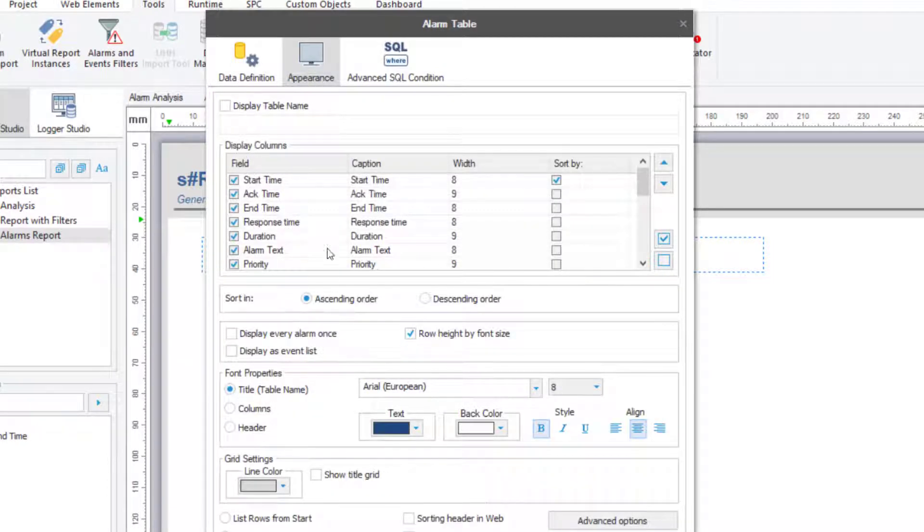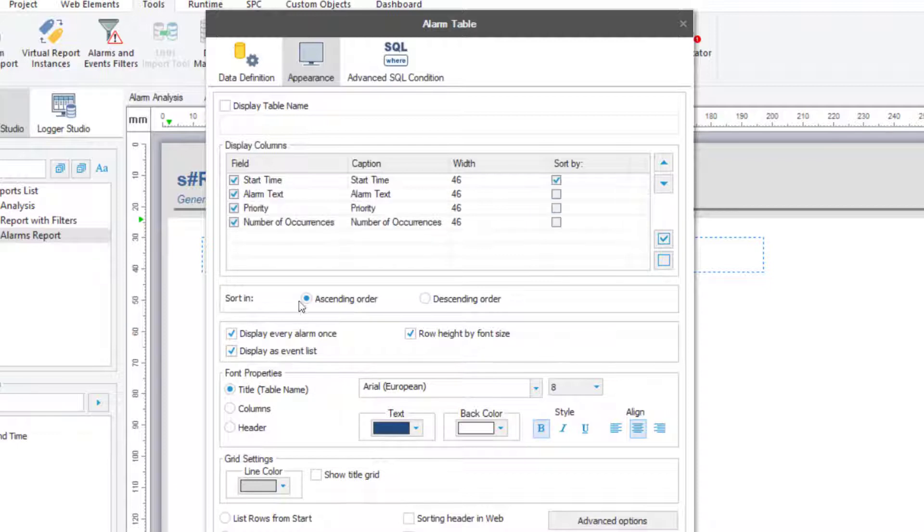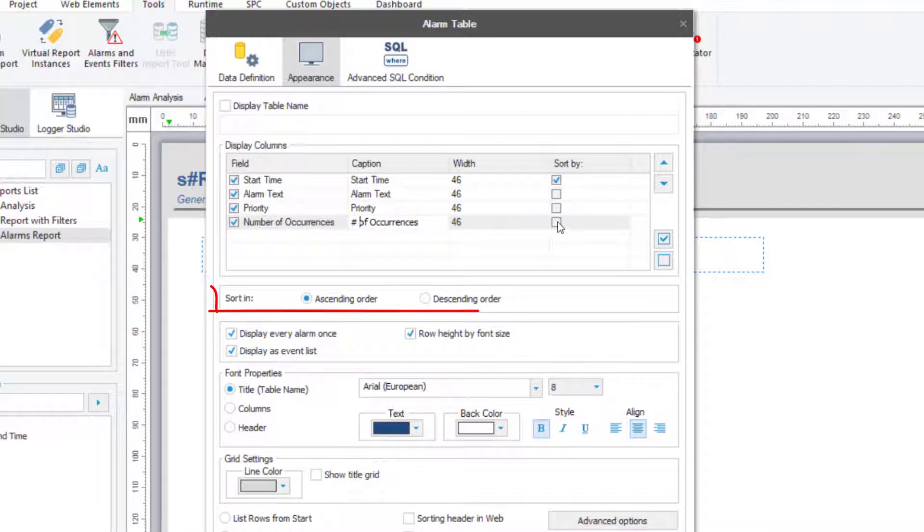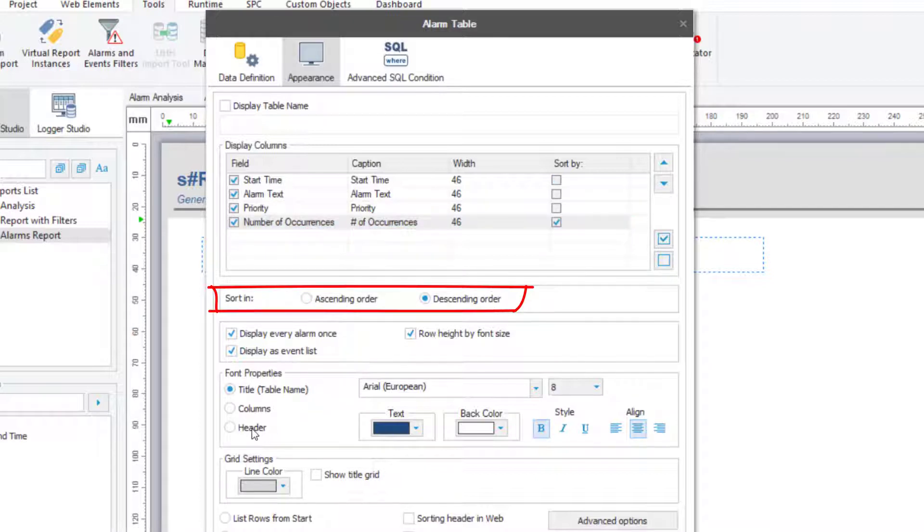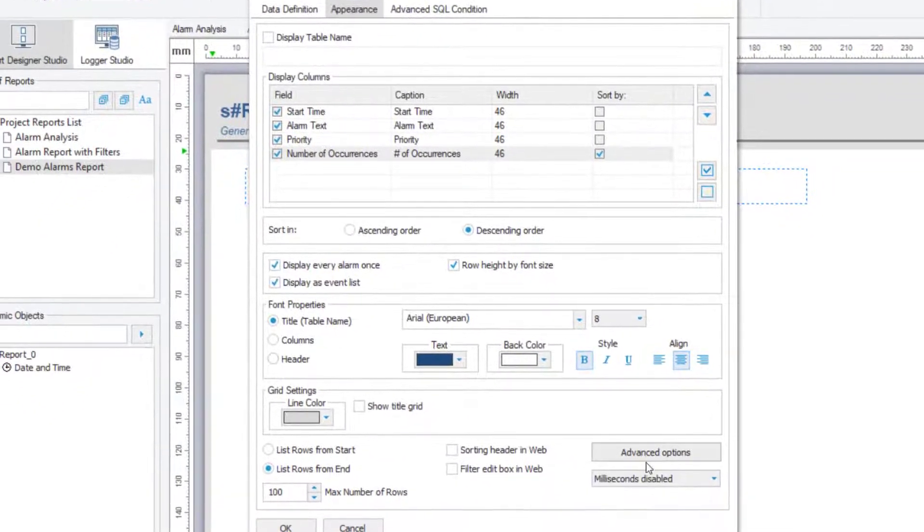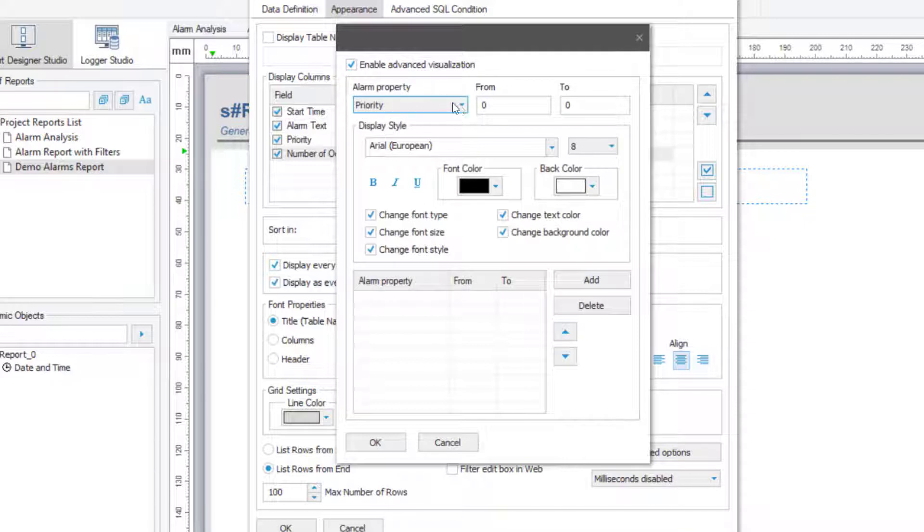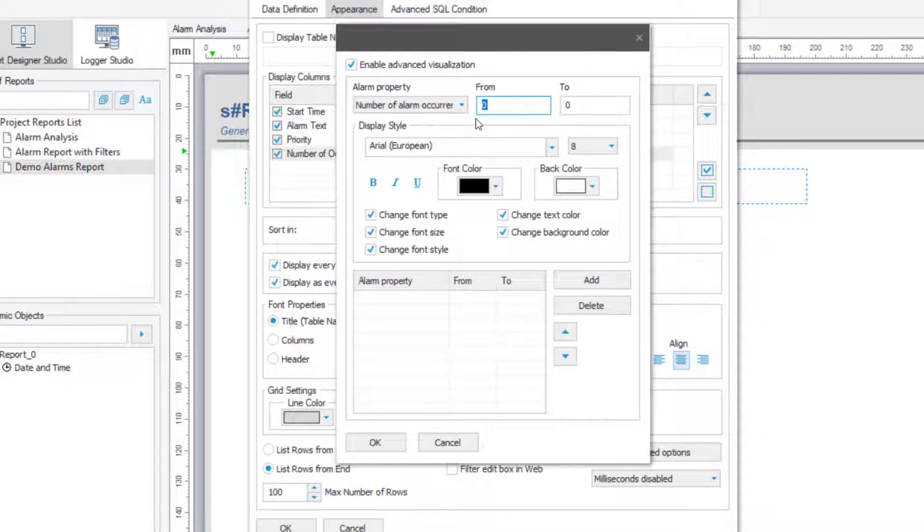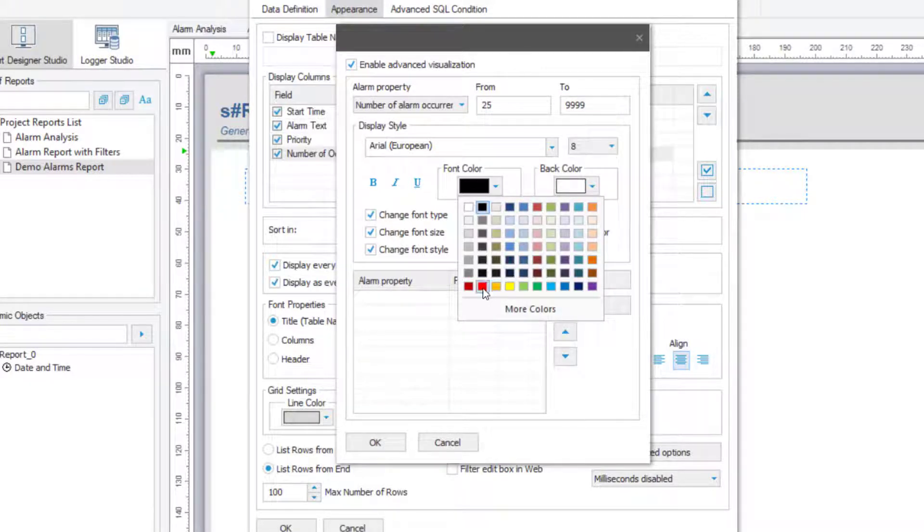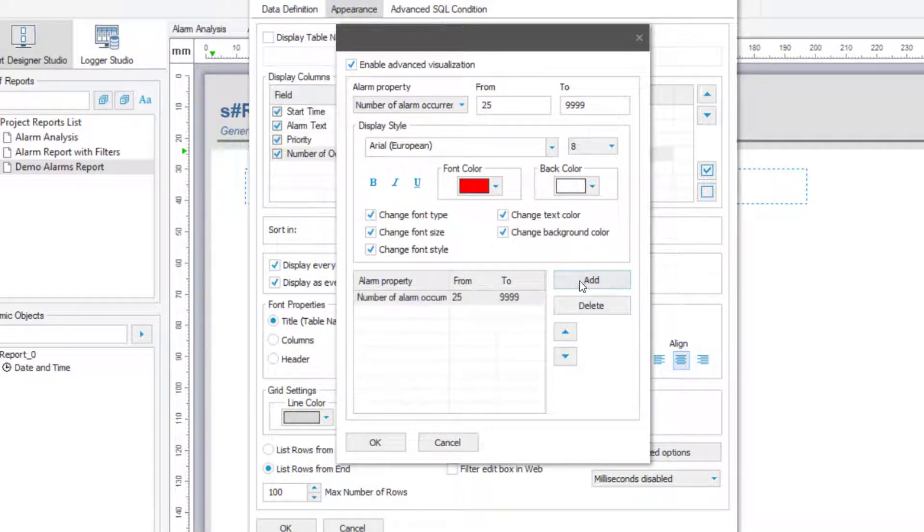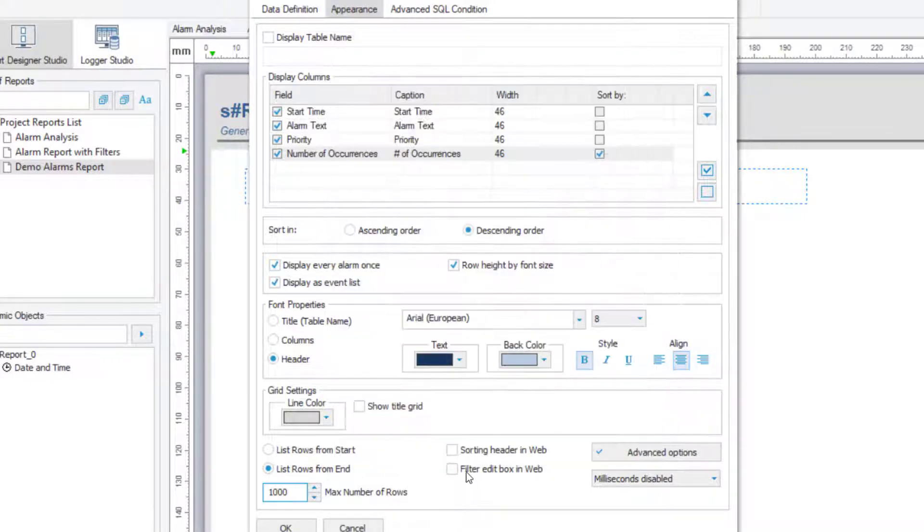Now let's set up the appearance of the table. Here you see all the available alarm fields for this data source. Since I want to summarize by the number of alarm occurrences, I'll choose the option to display as an event list, and then display every alarm once. While we're at it, let's do a Pareto sort by the number of occurrences descending. I'll do some basic formatting now. And then the last thing I want to do is highlight any alarms that occurred more than 25 times. I'll click on the Advanced Options button, and then set those to red text. Finally, I'll set a couple of options so that we can interact with the table on the Dream Report web portal.